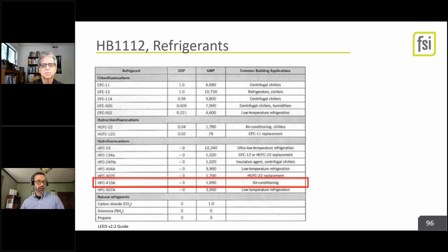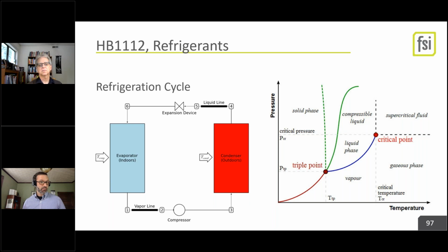So we did a really good job of getting our ozone depletion potential down with R410A, which is now really our industry standard. But the global warming potential is 1,890. And if you read other guides, up to 2,000 some over carbon dioxide. So it is short-lived, but very, very bad for global warming. Next slide. As we use refrigerants, we're making them into vapor, and then we're condensing them, and then we're evaporating them and making them vapor again. And that vapor leaks over time. Almost every refrigerant system that exists out there, with the exception of some centrifugal chillers that some manufacturers will certify will never leak. Every single one of them leaks. And particularly with things like VRF, that can be a substantial quantity of refrigerant. That's why it matters. Next slide.